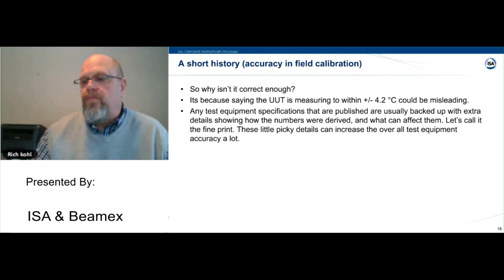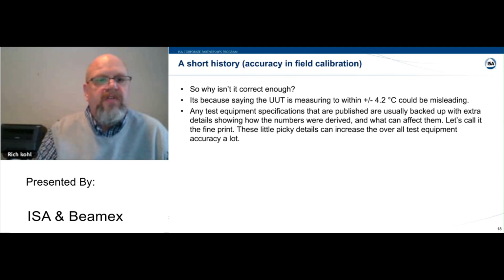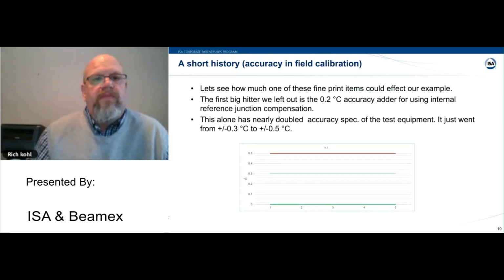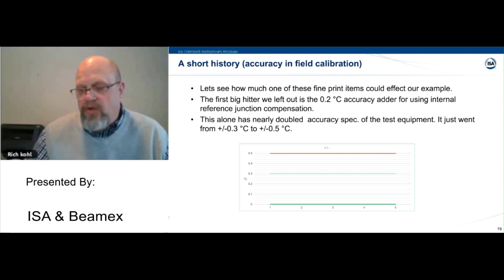So I think we can move forward and look at an example of one of these and how it affects the overall uncertainty. Let's say one of these fine print items could affect your example. We look at the big hitter we left out: the 0.2 °C accuracy adder for using internal reference junction compensation. Most everybody in the field is going to be using the calibrator's internal reference junction compensation, so it's almost a default add for the field.